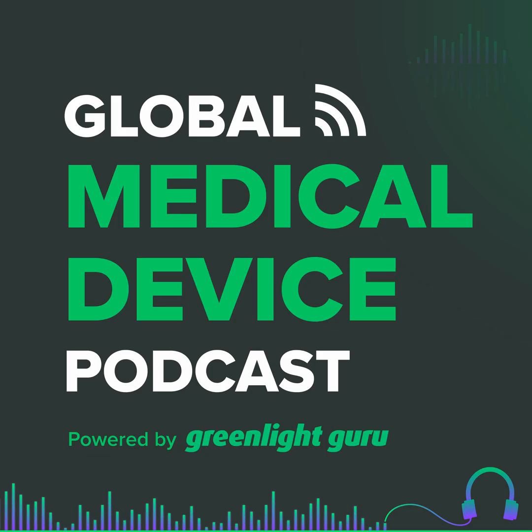Now, technically speaking, that's actually not correct, even though it's coming directly from the FDA, or at the very least, it can be interpreted different ways. Remember, Etienne, regulation is about two things. It's about the interpretation of words and our ability to defend our interpretation. So when FDA says, and this is in FDORA, any medical device on the market may use a PCCP to make changes without requiring a new pre-market submission, there is a new pre-market submission, but it just happens to be within the context of the original pre-market submission. So maybe that's an overly technical aspect, but I do think it's important to remind my FDA friends that are listening to this audience that it's not just important for industry to understand the verbiage here, but FDA as well.